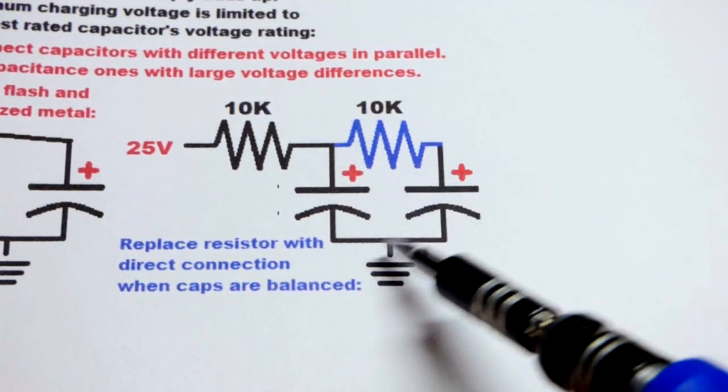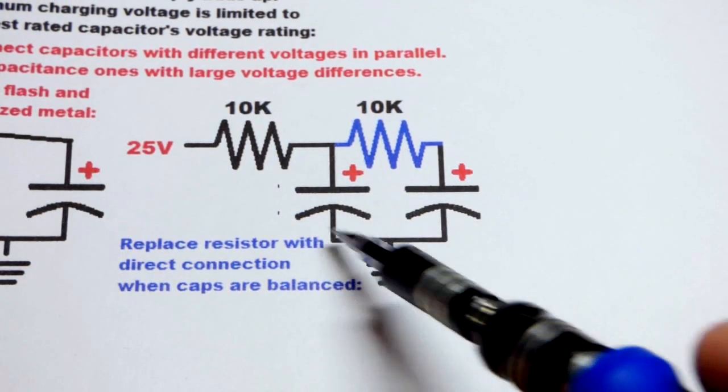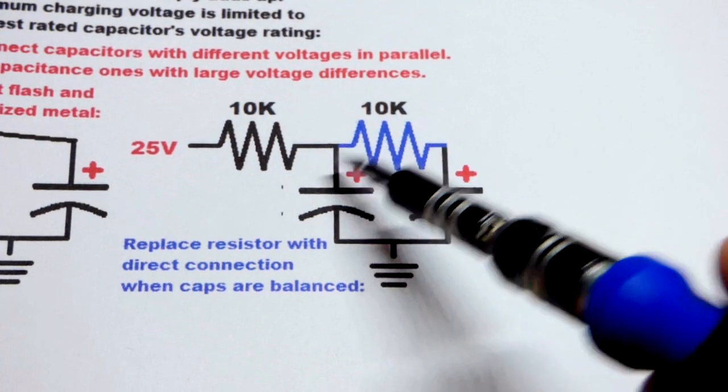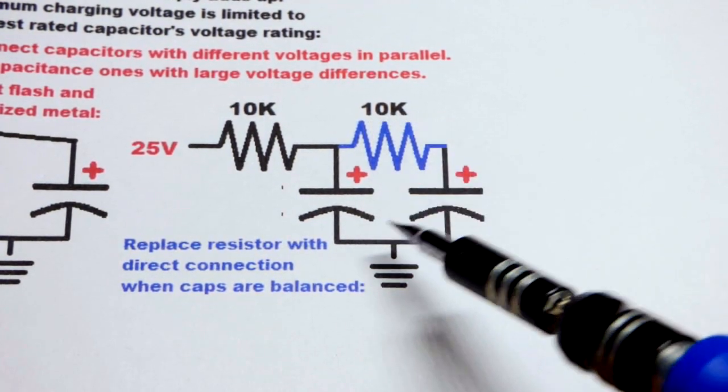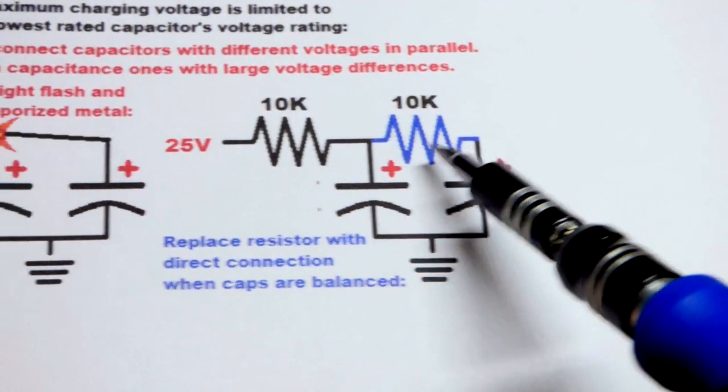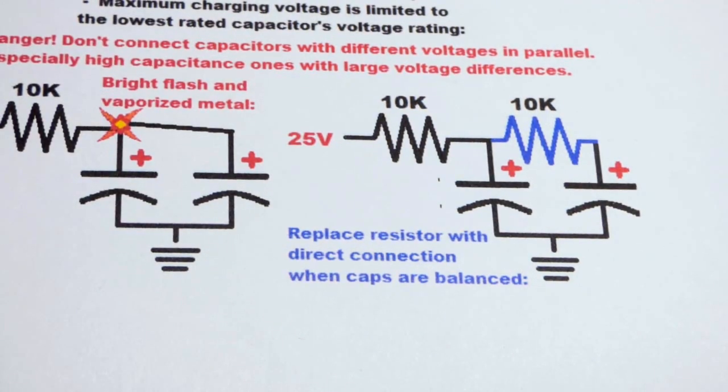And a good way to do that is beforehand, again, you can connect one side, or you could connect that side, but it's usually better to connect ground first. And then, you could use a resistor, a fairly high value resistor, until they equalize. And then, you can substitute that resistor with a jumper. Once they're equalized, no problem.